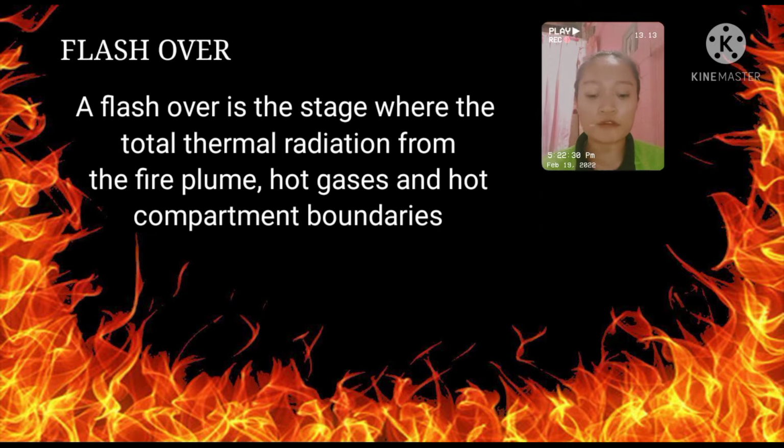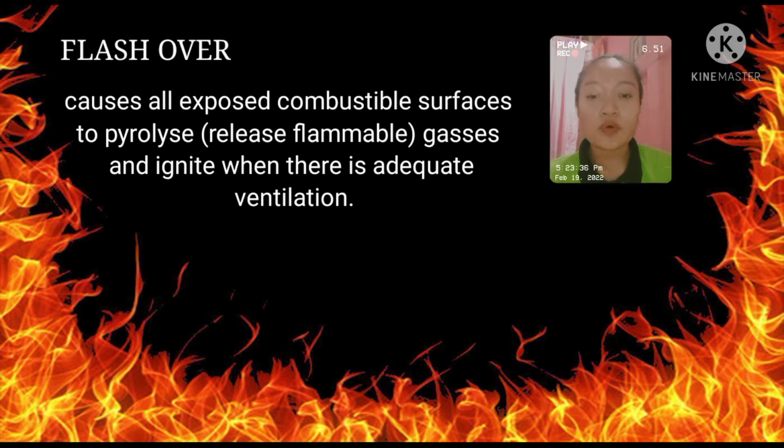Next is flashover. A flashover is the stage where the total thermal radiation from the fire plume, hot gases, and hot compartment boundaries causes all exposed combustible surfaces to pyrolyze, release flammable gases, and ignite when there is adequate ventilation.